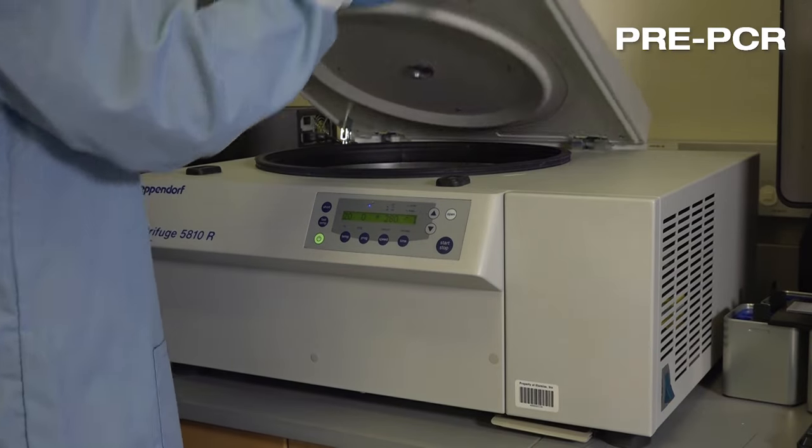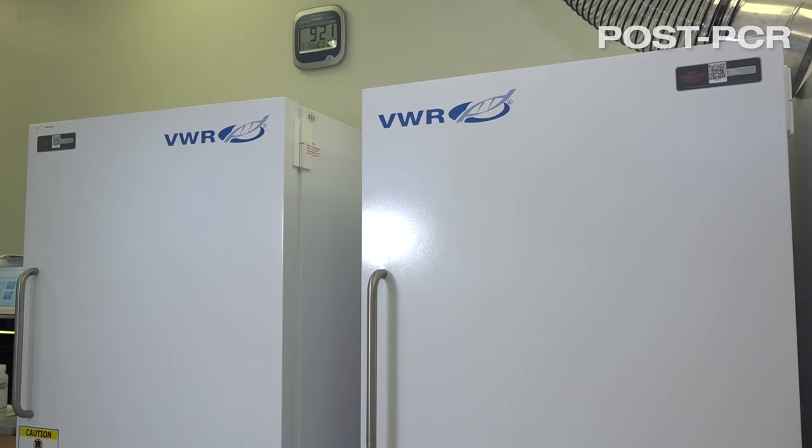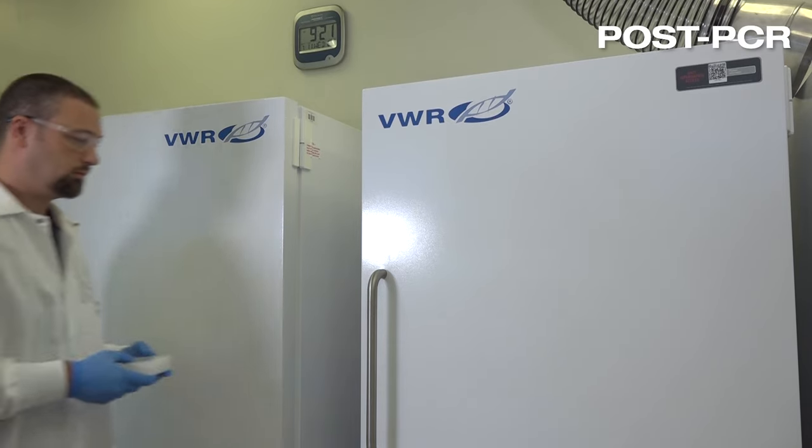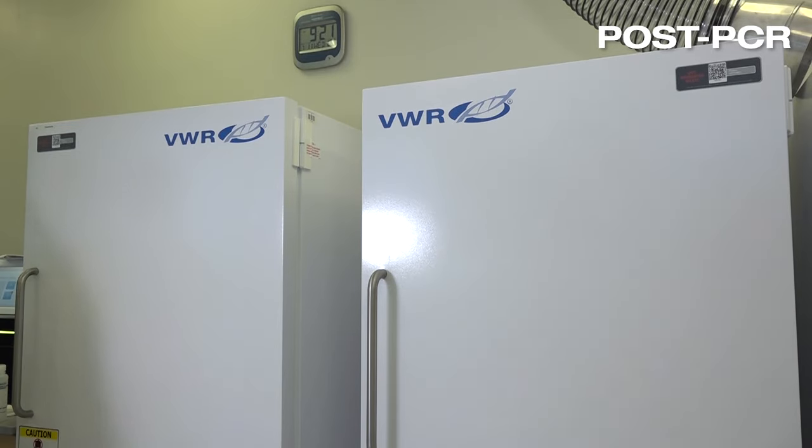Equipment should not be shared between the pre- and post-PCR areas. Instead, use separate, dedicated equipment in the respective pre- and post-PCR areas, including refrigerators and freezers.